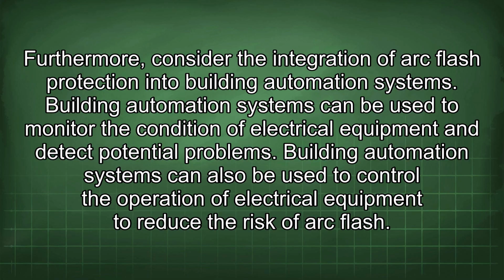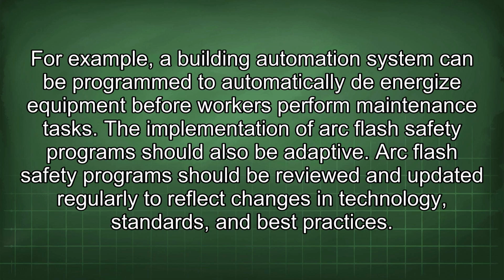Building automation systems can be used to monitor the condition of electrical equipment and detect potential problems. Building automation systems can also be used to control the operation of electrical equipment to reduce the risk of arc flash. For example, a building automation system can be programmed to automatically de-energize equipment before workers perform maintenance tasks.